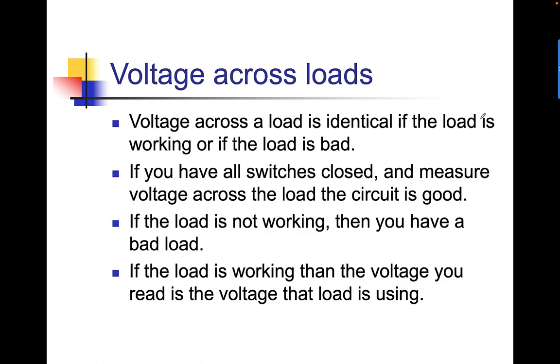Voltage across a load is identical whether the load is working or bad. If the load is working, it's going to be, let's say, 120 volts across a light bulb. If the load is bad, it's still going to be 120 volts because the load is open. The only difference is, if it's working, it's generating light and heat. If you have all the switches closed and measure voltage across the load, the circuit is good. If the load is not working, then you have a bad load. If the load is working, the voltage you read is the voltage that load is using.